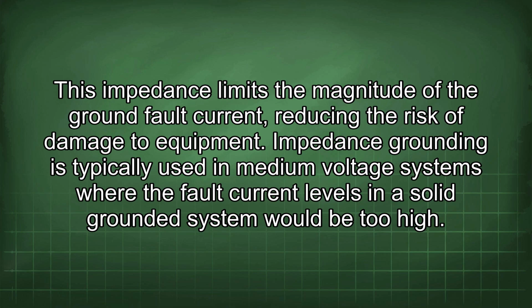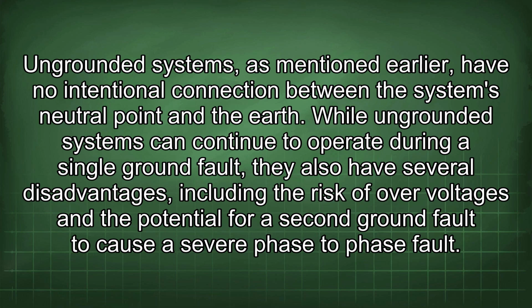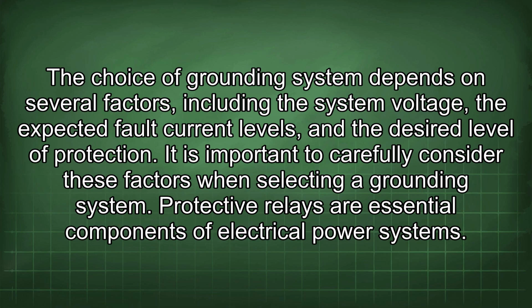Ungrounded systems, as mentioned earlier, have no intentional connection between the system's neutral point and the earth. While ungrounded systems can continue to operate during a single ground fault, they also have several disadvantages, including the risk of overvoltages and the potential for a second ground fault to cause a severe phase-to-phase fault. The choice of grounding system depends on several factors, including the system voltage, the expected fault current levels, and the desired level of protection. It is important to carefully consider these factors when selecting a grounding system.